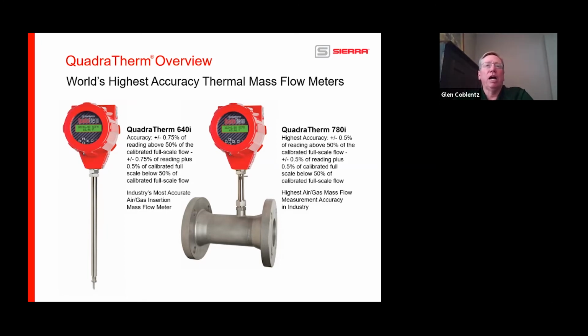And I wanted to take a little bit of time here to go through the accuracy statement, because I get this question probably at least once a day about, well, what would be my uncertainty at this calibrated flow rate or this calibrated full scale. So if you see here, you have the two different accuracy statements: 0.75% across the whole range. And then below 50% of the calibrated full scale, you add a 0.5% of calibrated full scale. And then over here with the 780i, since we absolutely know the inside diameter of the pipe, it's 0.5%.